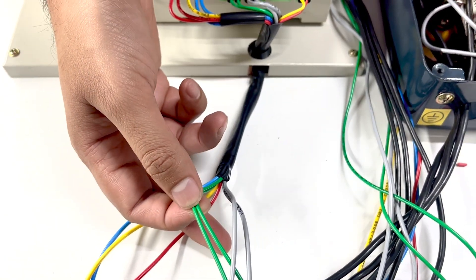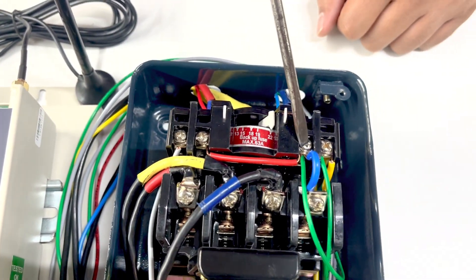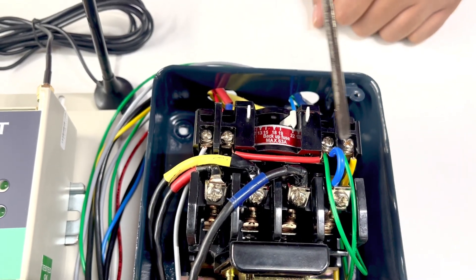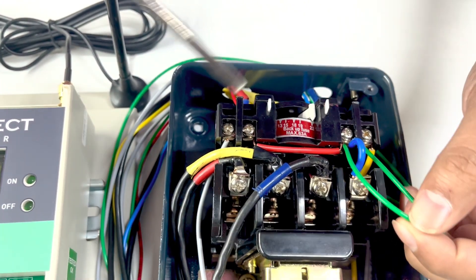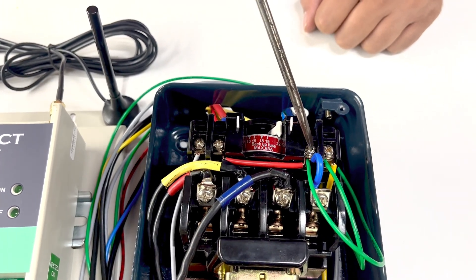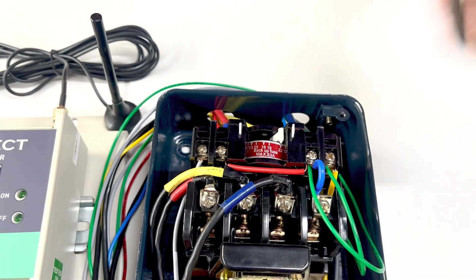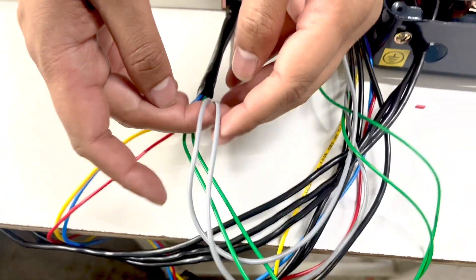You have a set of two green wires. These green wires should be connected in parallel to the start push button. These two points are the start push button points on the starter. The two green wires coming out of the smart connect mobile controller should be connected to these two connectors. None of the existing wires should be removed — the green wires are connected on top. One green wire goes to the first connector and the second green wire to the second connector.